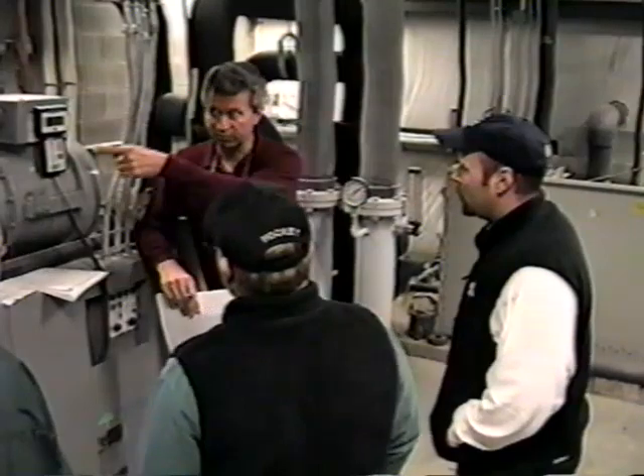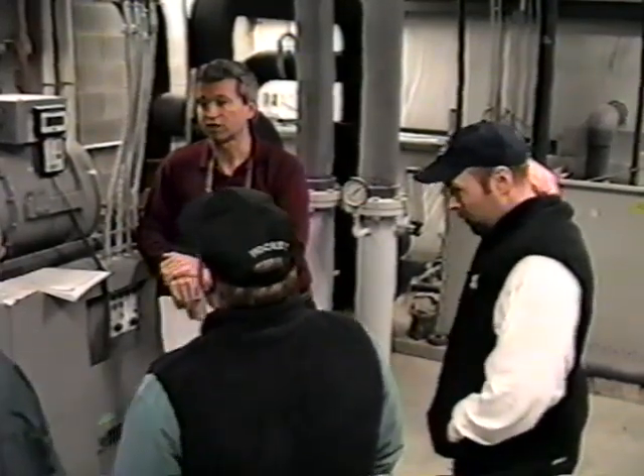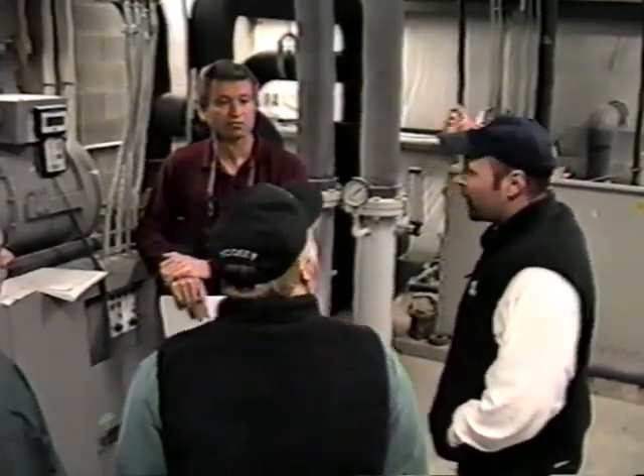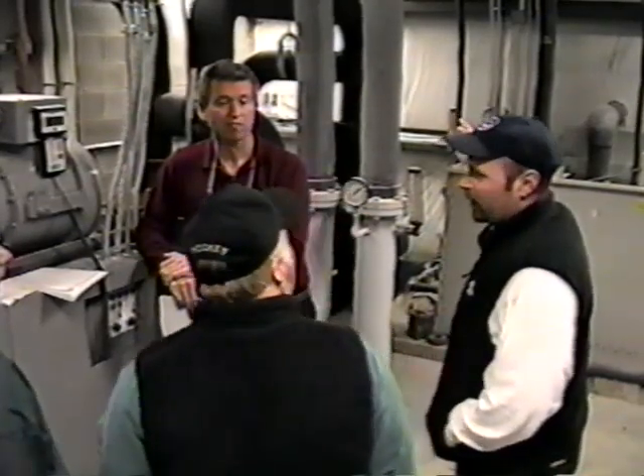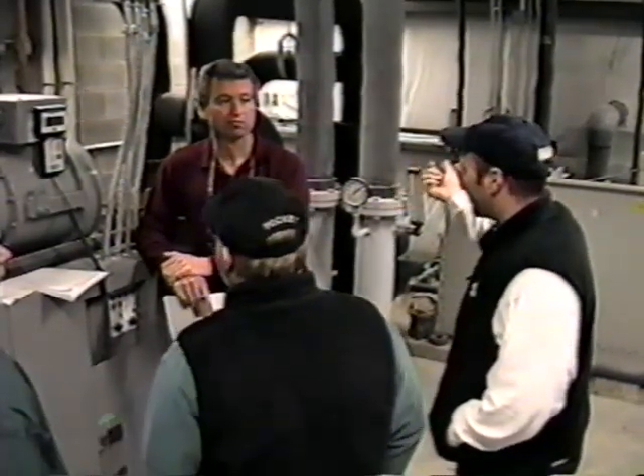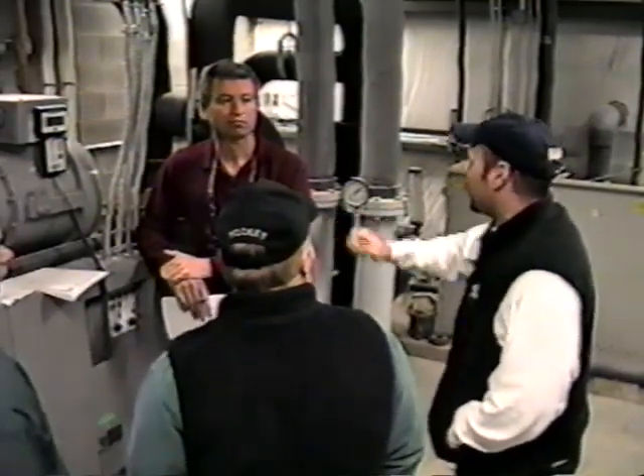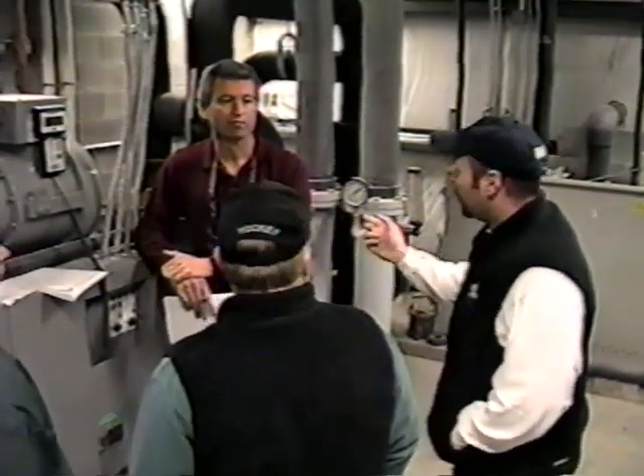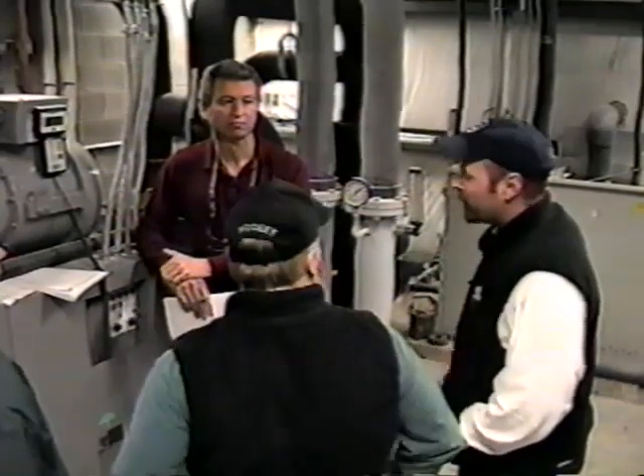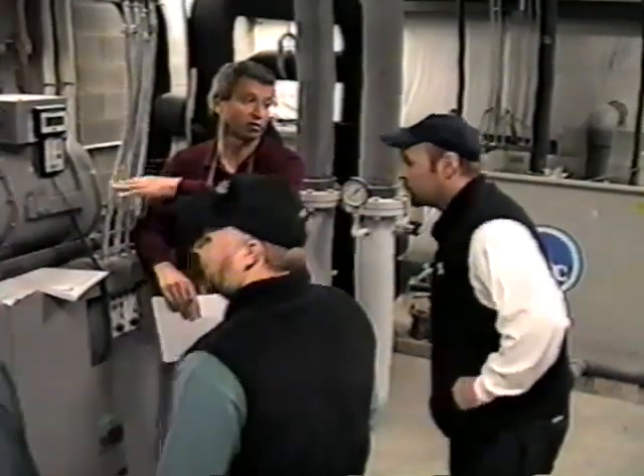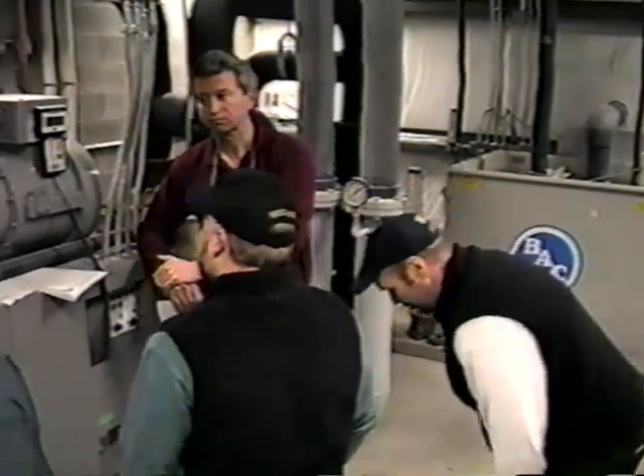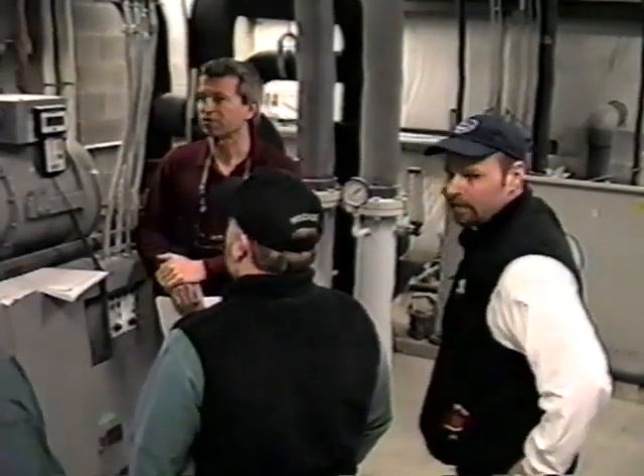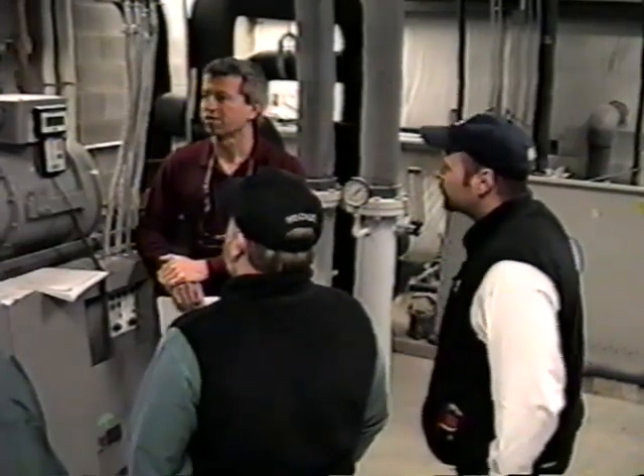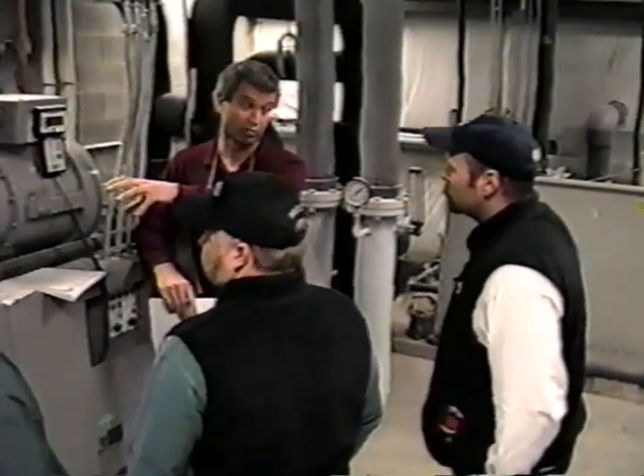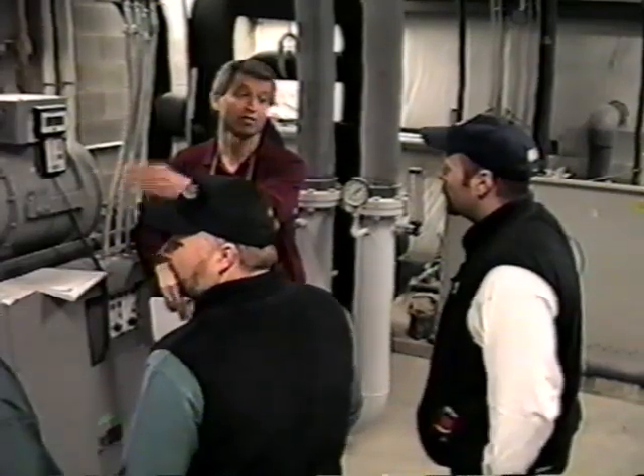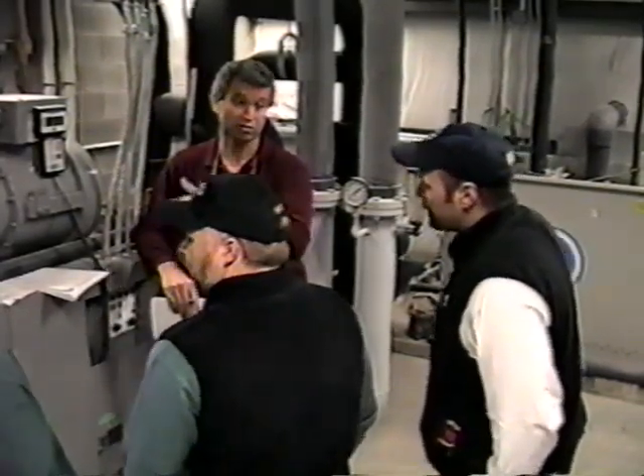And I'm not sure why. That may have been an alarm condition or something that was not reset for a while. Yeah, over there we could change our hours. Compressor one is the lead compressor, two is the lead compressor, so whatever starts, it backs up and does it by itself. Yeah, you can set a particular one to be the lead. Well, if it does it by itself, it's fine. So you want to balance it out if you can. And remember, it's going to be closer to the actual hours plus the number of starts. Okay, that sum is right.